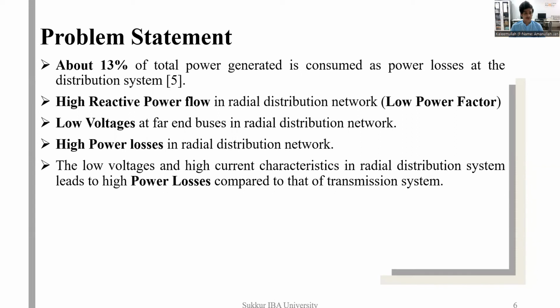So what is the problem statement? About 13% of the total power generated is consumed as power losses in the distribution system. There is a high reactive power flow in the radial distribution network, due to which there is a low power factor. There are low voltages at far end buses in the radial distribution network, and high power losses. The low voltages and high current characteristics in the radial distribution system lead to higher power losses compared to those of the transmission system.